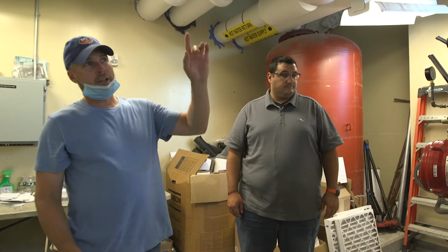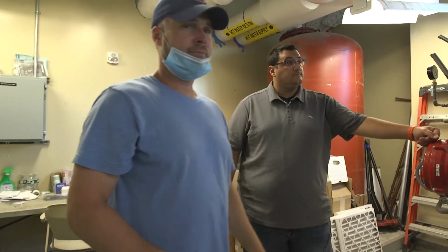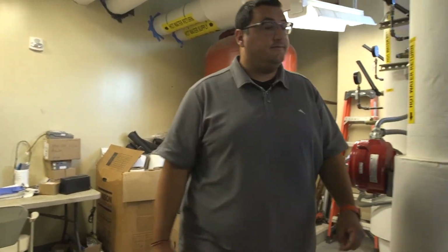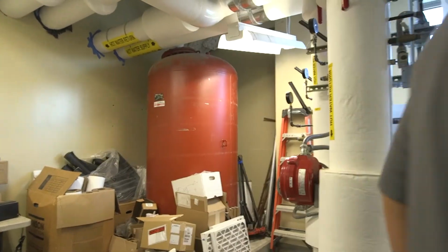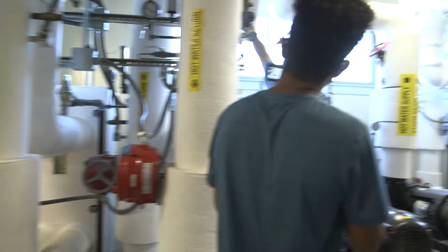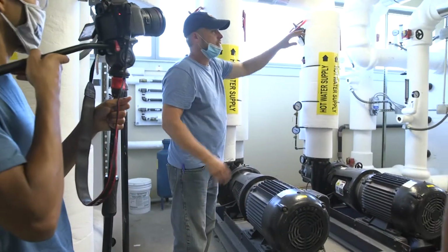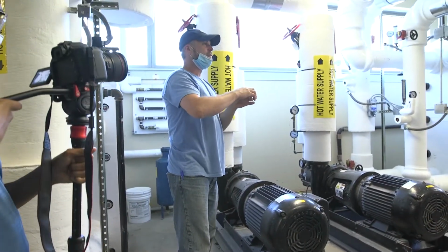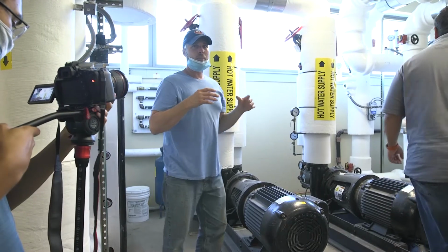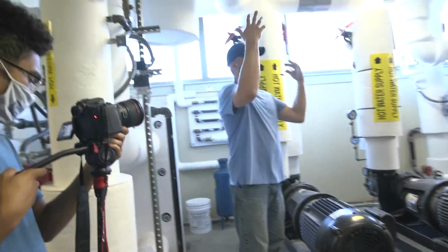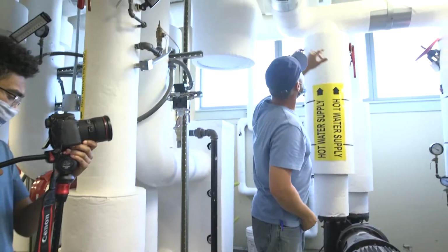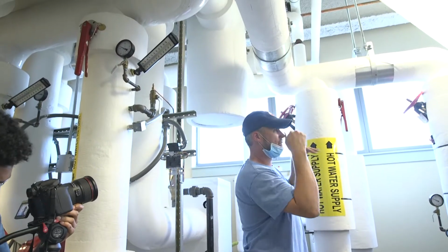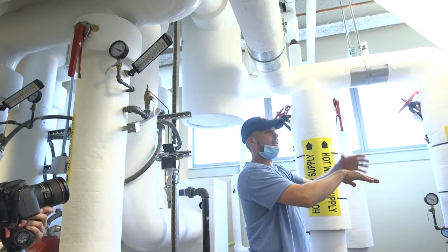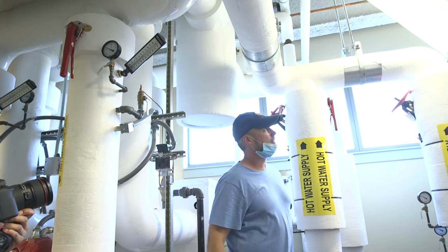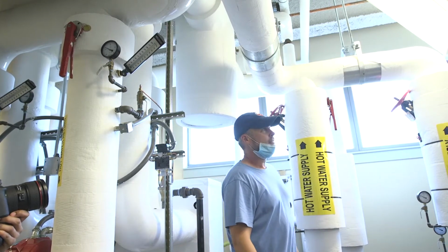You have air separators that are part of the system. Oh, I didn't see those. An air separator and an air separator. They have automatic air vents on them. The purpose of the air separator is just to extract the air from the water. There's automatic air vents up top, so as the water falls, the air rises and bleeds out of the vents. And that's really it.